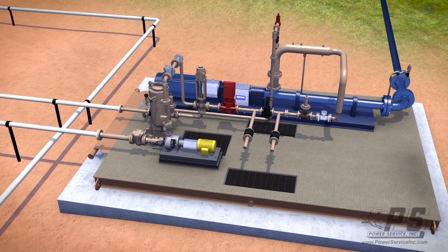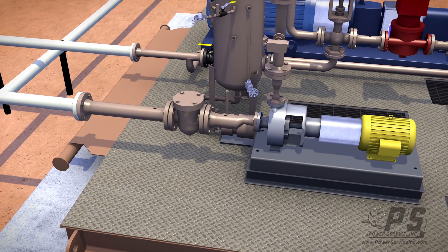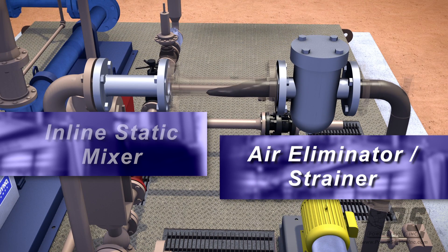In a standard LACT unit, oil that's been processed through our wellhead separation equipment and into a holding tank enters the LACT through the charge pump. It passes through the BS&W, checking for basic sediment and water in the oil. It then moves to the inline air eliminator strainer and then passes through the inline static mixer.